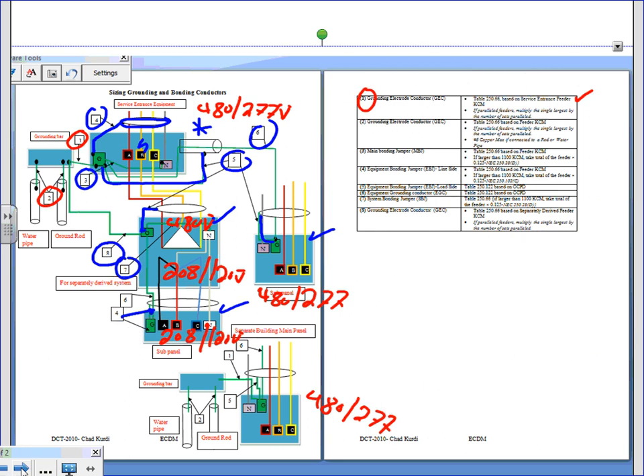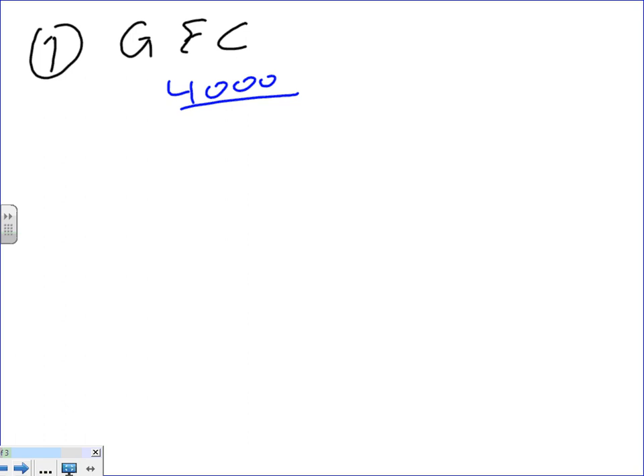When we go size them, my friends, we're going to go to the first thing. We're going to size the 4000, number one. So number one, right? What was number one, guys? Grounding electrode conductor. I want you to look where number one is located, guys. When we size number one, we size it based on the service conductors coming to the building. So I have a 4000 amp service. I'm going to parallel 12 runs. I have to have the conductor size, guys, for this one. 12 runs. I end up with 333 amps, 333 amps, right?